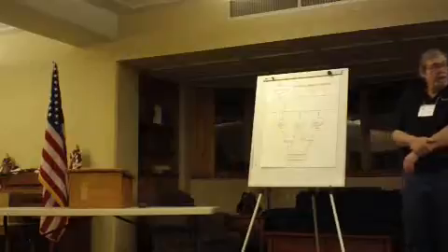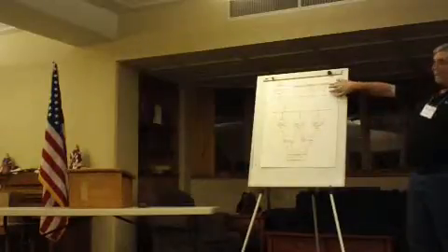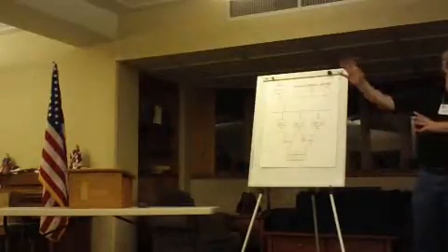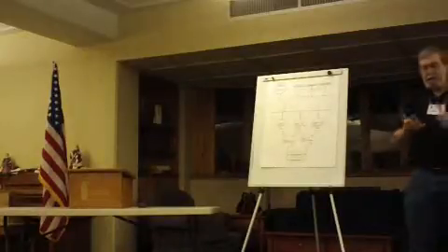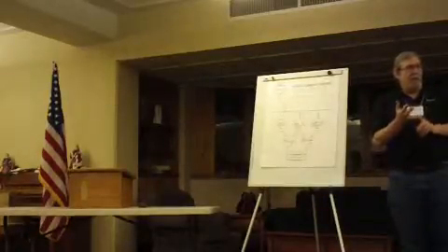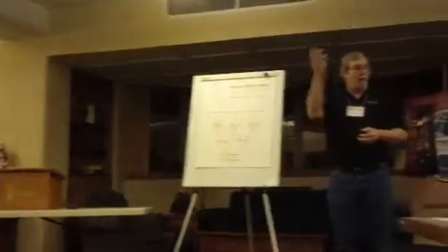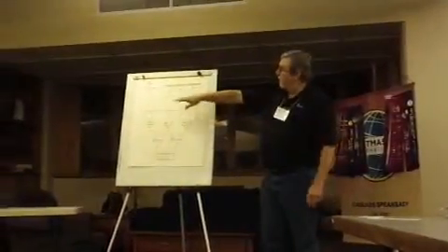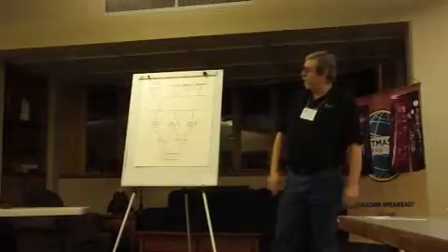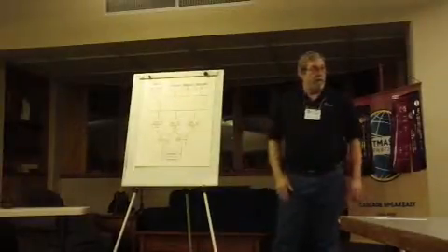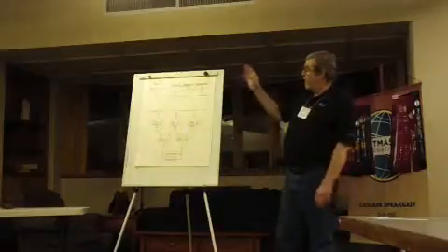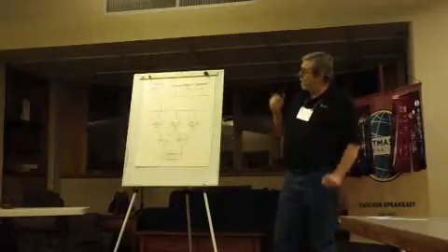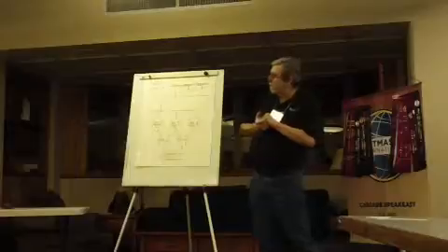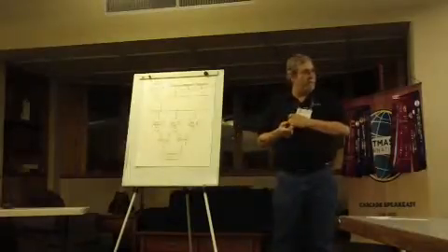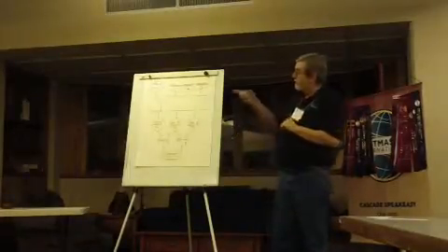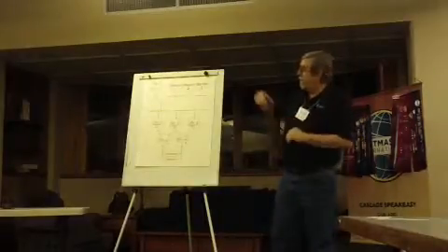If power from that utility comes back on in 3 seconds, these generators do not start. We stay on utility. This allows us to not have a lot of generator starts, a lot of problems with power coming on and off to the data center. So we count to 3. Now, if that counter goes past 3, all the generators at the site will start up, and they come up to speed - usually that takes approximately 20 to 30 seconds at the site that I'm at. That means these things have to fire up and come up to full speed.